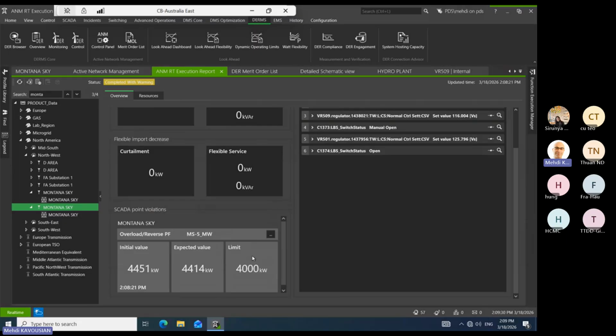So let's say you want to limit to 1 megawatt. It targets 3% lower than this because of, let's say, inaccuracy in data, or when you send a command, in a few minutes maybe it still changes, and then you don't want to try it again.